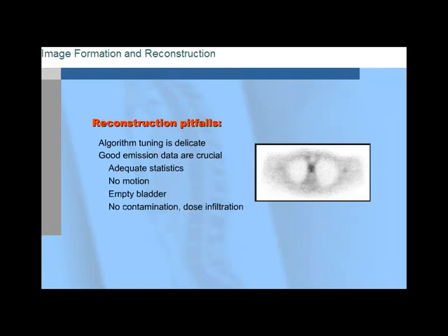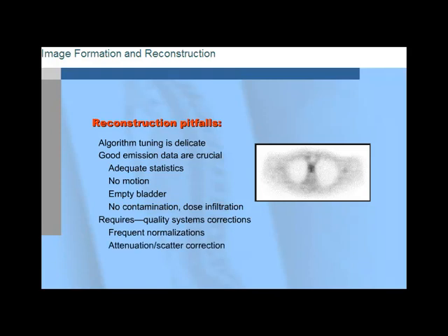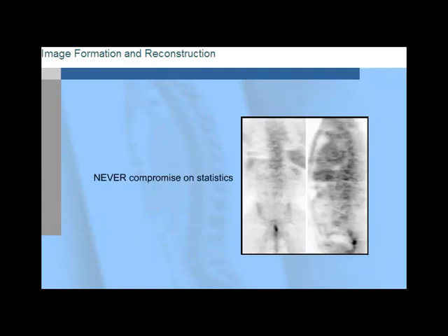No dose infiltrations, etc. Furthermore, high-quality system corrections, including frequent normalization, attenuation correction, and scatter correction, are also desirable. Finally, never compromise emission and transmission statistics, especially on heavy patients.